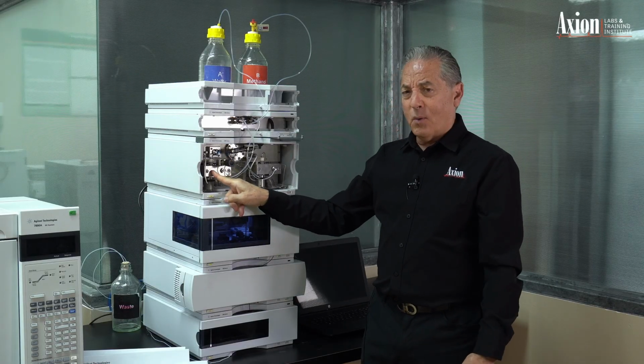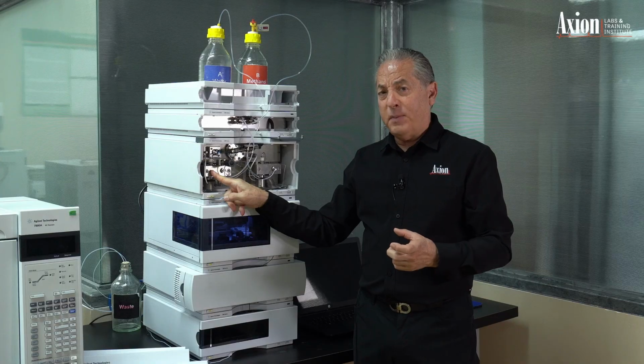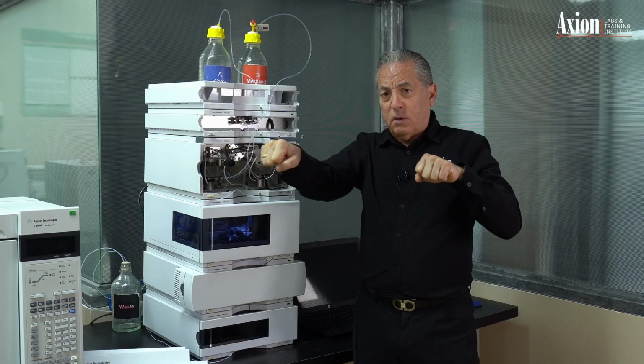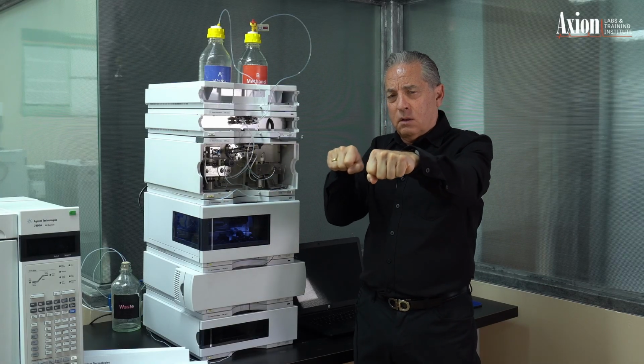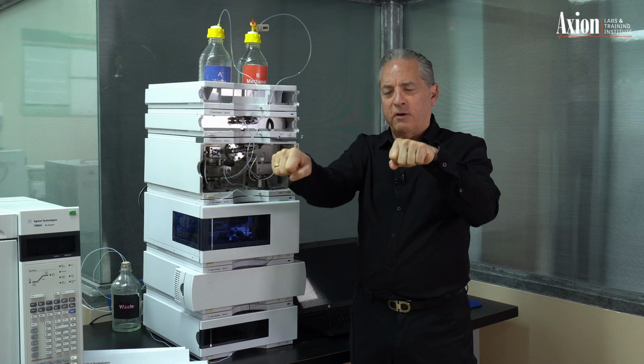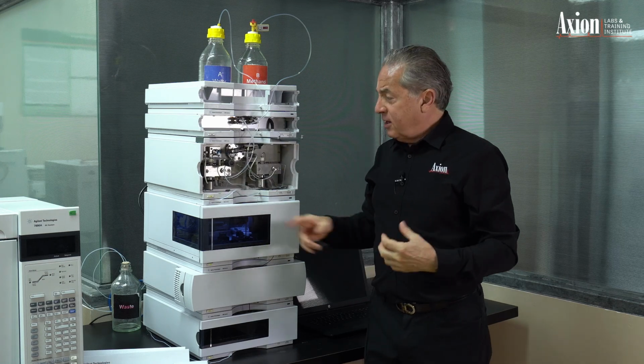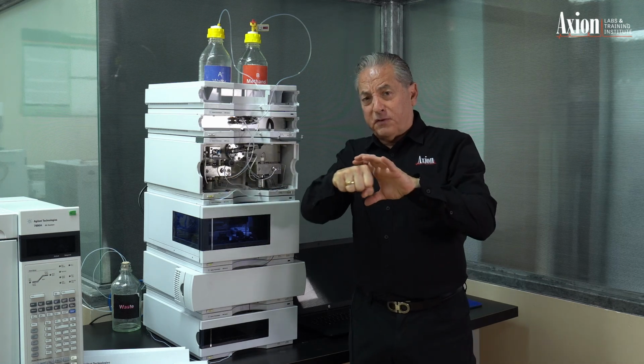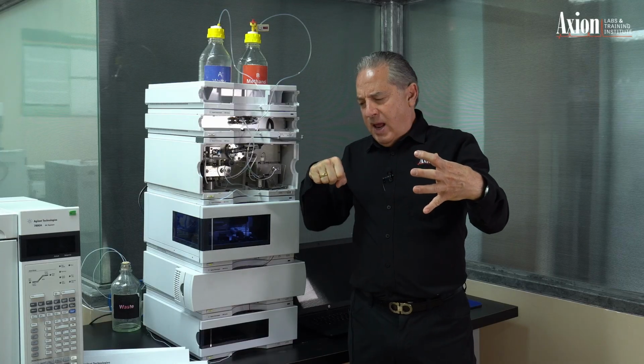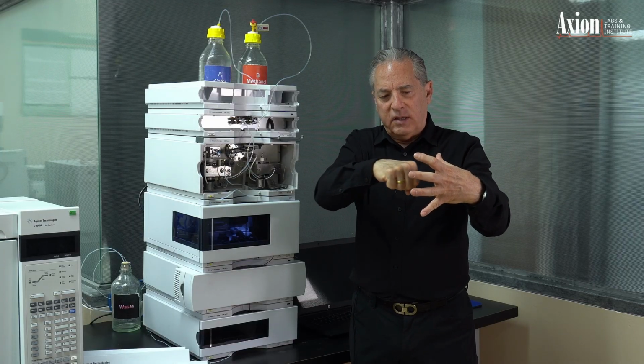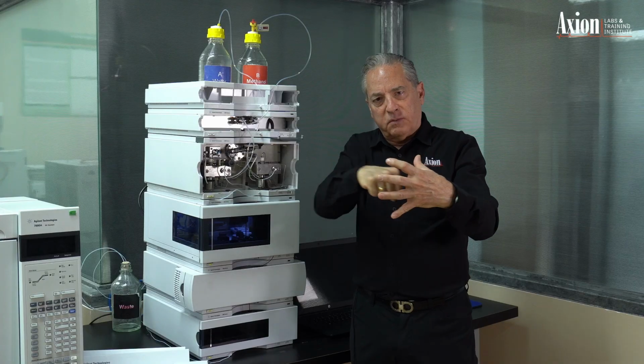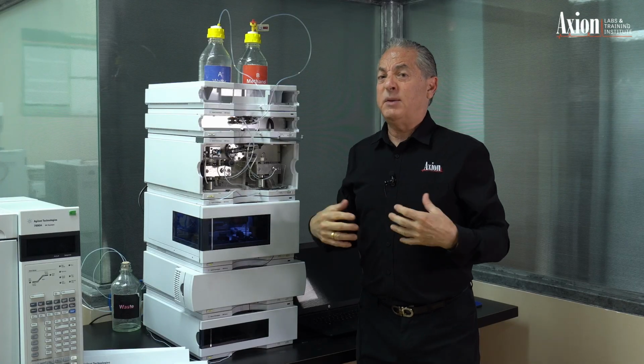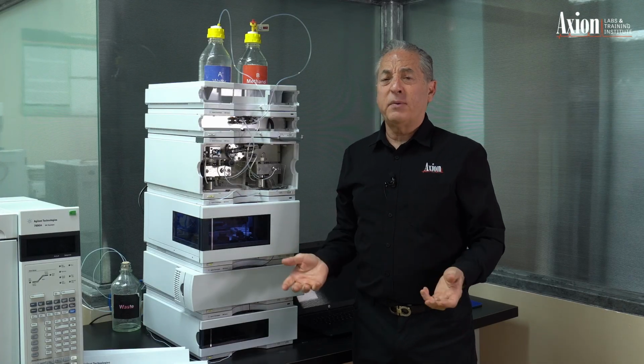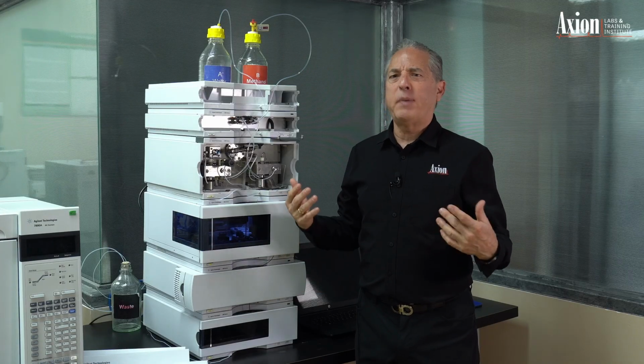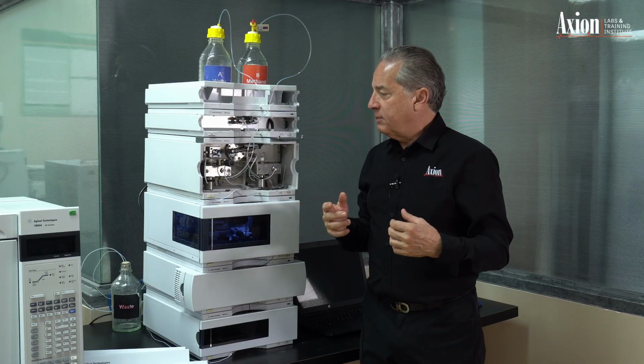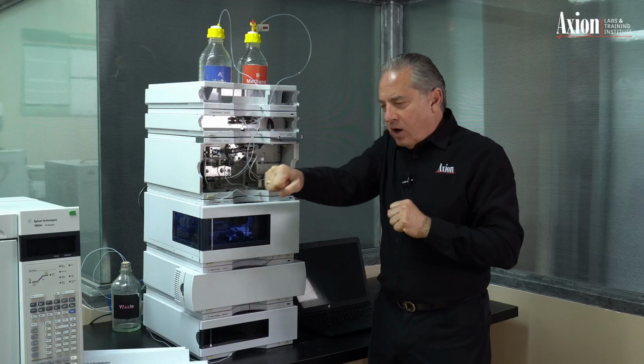So piston number one, this is a sapphire piston. And what it's doing is it's sort of back there. There are two pistons, pistons 1 and 2, pushing back and forth. And you can imagine that like a syringe. So this syringe is filled with 100 microliters of liquid, and then the piston pushes in, displaces it, and then pulls back, refills, pushes back. So that's what's called a reciprocating piston pump. Just about every pump on the market today, I think every pump on the market today, is a reciprocating piston pump.